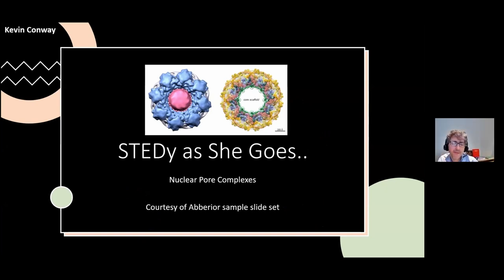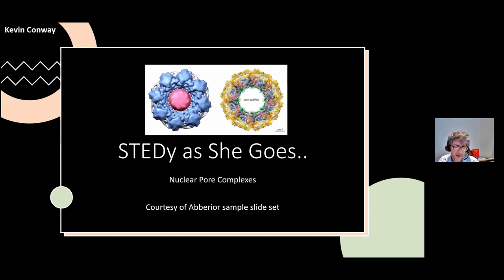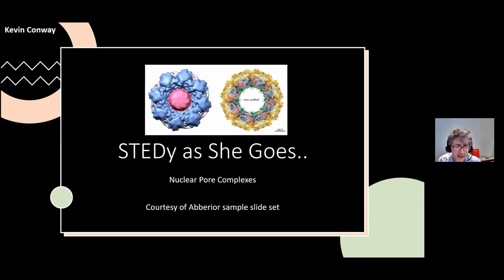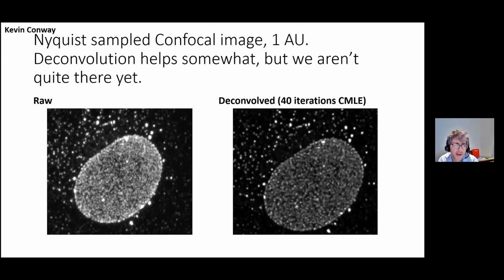When we do this in the facility, we give people a walkthrough of what brings them to a super-resolution scope — they need to have a biological target of interest. I pulled out the Leica sample slide — a stain of a nuclear pore complex, which in the cartoon is about 20 nanometers on the side of the donut. The whole structure is below the diffraction limit, making it an ideal structure to image. I got the best possible confocal image on the SP8, sampled at Nyquist and did deconvolution — which helped a bit, but we're still hovering near the diffraction limit.